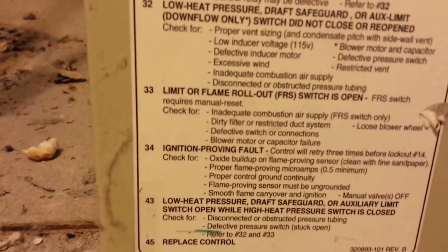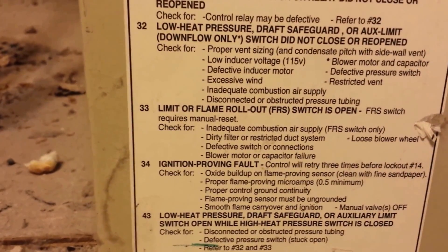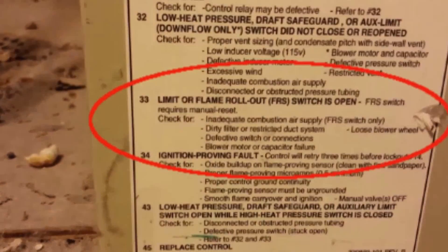Then on your panel down here you just look and you'll be able to find the code. Mine was number 33, and that's the limit or flame rollout FRS switch.